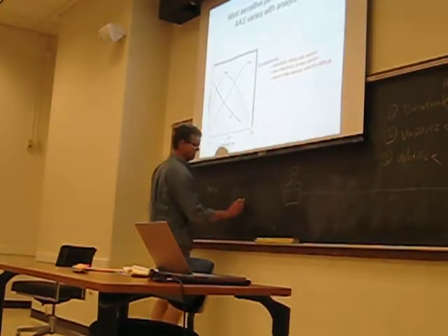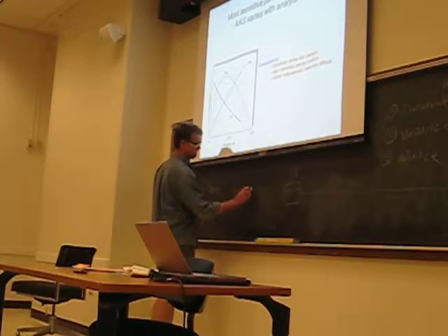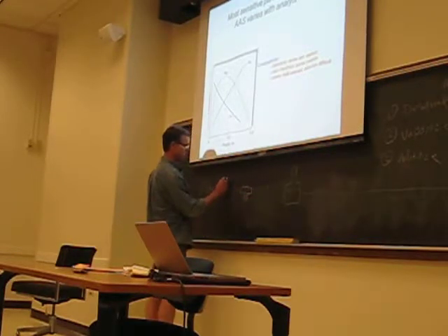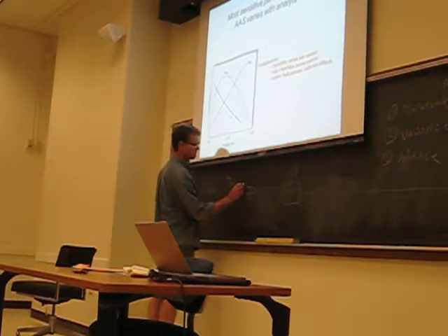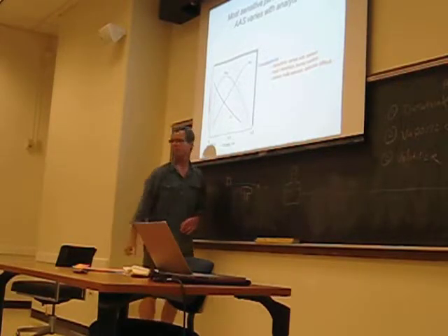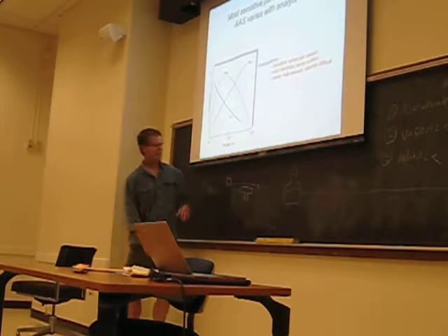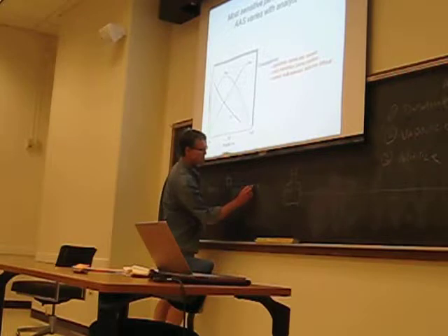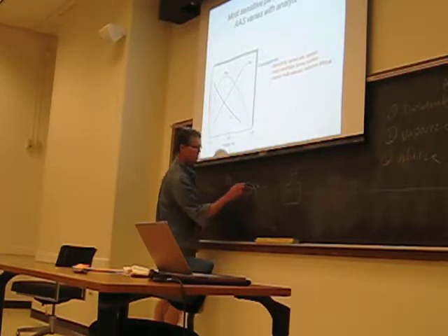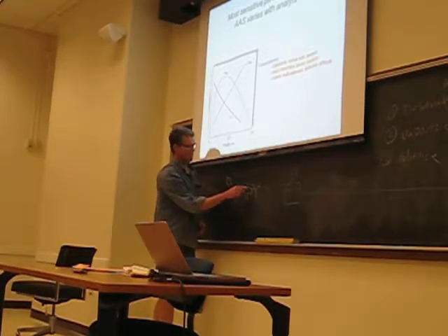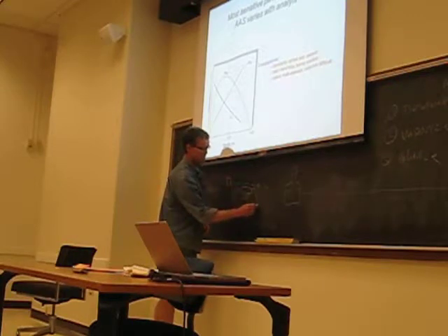So for us, you have your burner head like this, and over here is the instrument, you don't see it, but a light is shining out and going across the burner head like that, right? And when they call it the burner height, that's the distance between the light path beam and the top of the burner head.